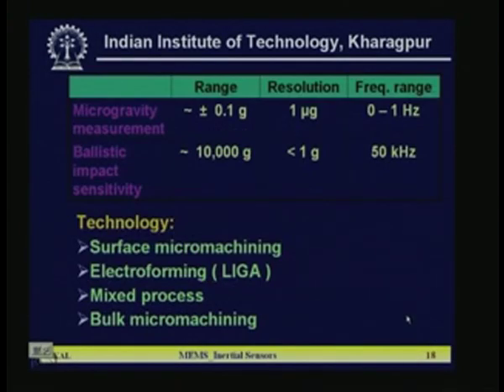Now, here just mention the typical range, resolution and frequency range of 2 classes of accelerometers used for microgravity measurement and ballistic impact sensitivity. So, for microgravity measurement, the range is plus minus 0.1 g and the resolution required is obviously 1 micro g if the total range is 0.1 g, and its frequency range is 0 to 1 hertz.